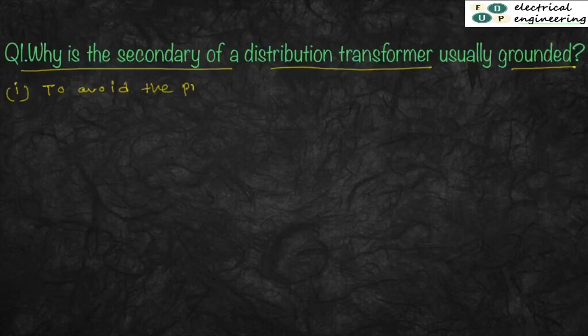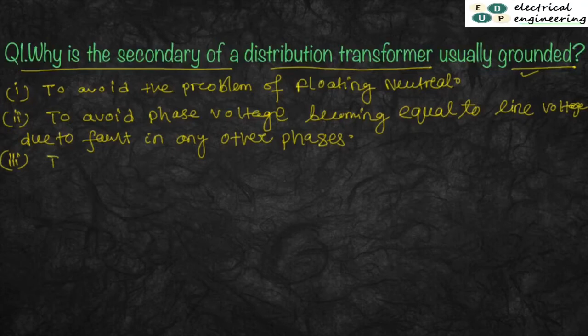And the second one is to avoid the phase voltage becoming equal to the line voltage due to a fault in any other phase. And the third one is to discharge lightning surge to ground. So these are the reasons for which the distribution transformer secondary is usually grounded.